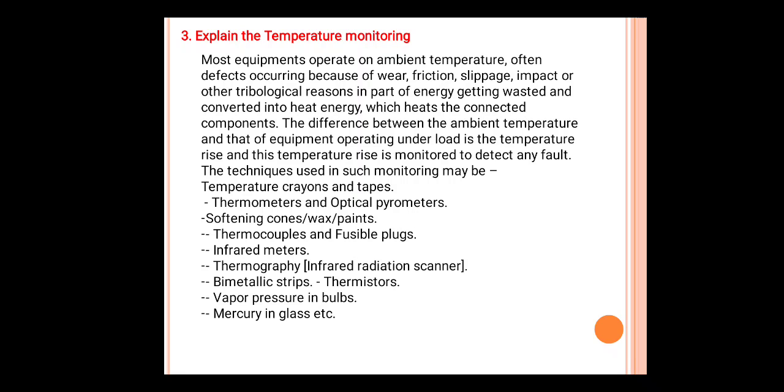Part of the energy gets wasted and converted into heat energy, which heats the connected components. The difference between the ambient temperature and the temperature of equipment operating under load is the temperature rise, and this temperature rise is monitored to detect any fault.